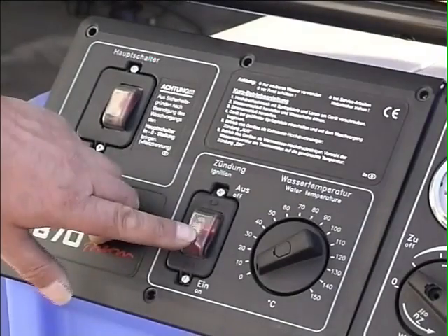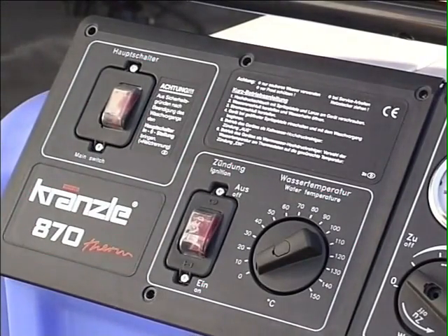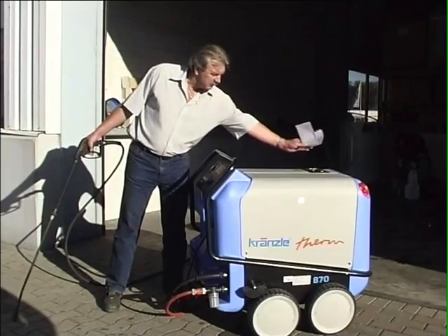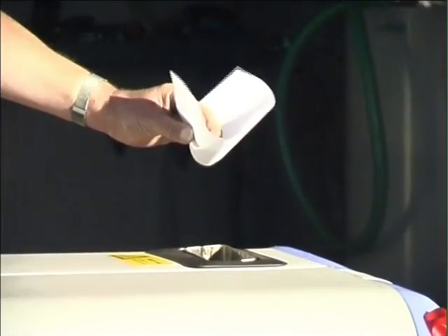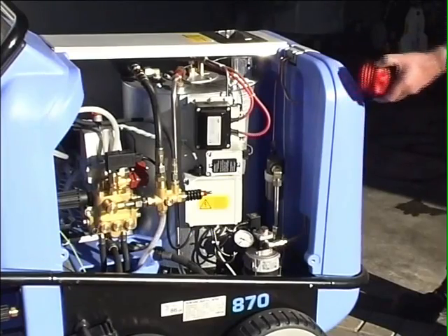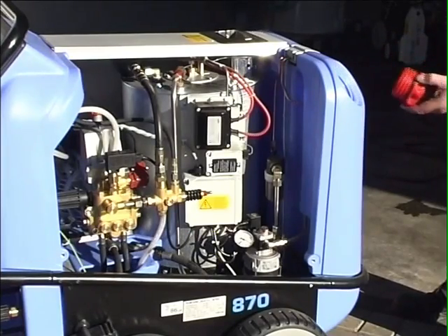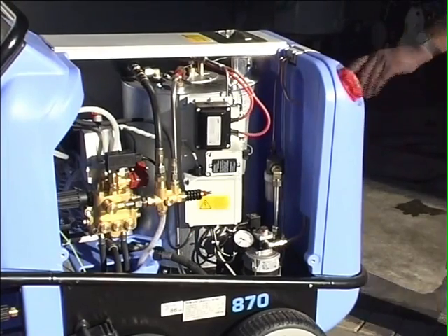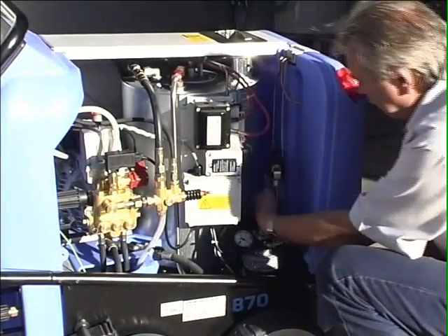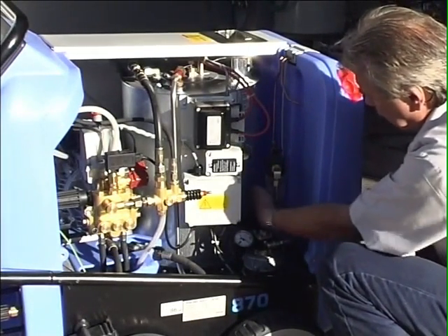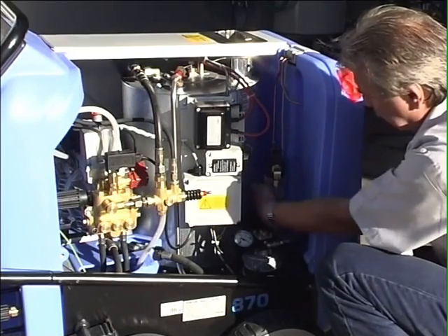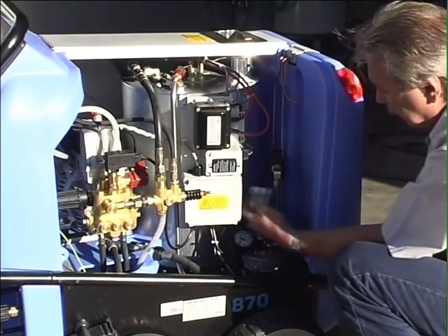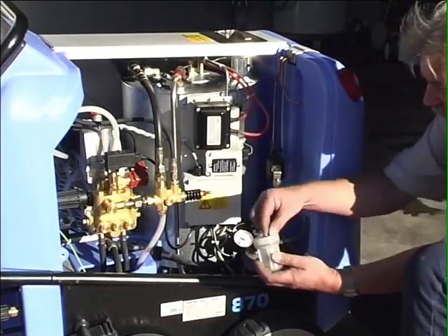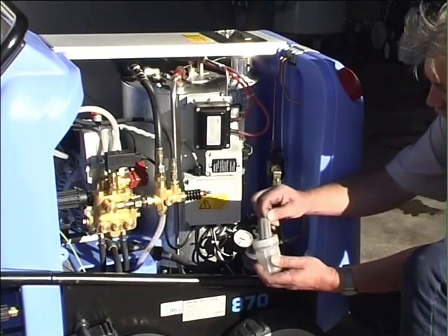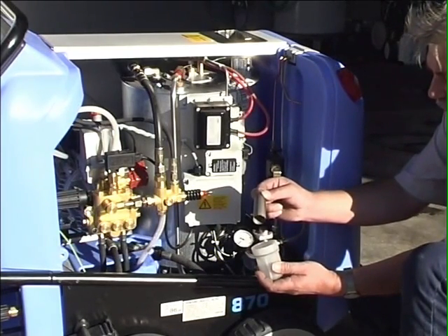If the burner is turned on but the waste gas is still cold, it can be attributed to the following causes. Check to see whether there is enough fuel in the tank. The fuel filter may be dirty. If it is, clean it. Remember to clean the fuel tank as well. For this purpose, you must open the drain screw on the bottom to empty the tank.